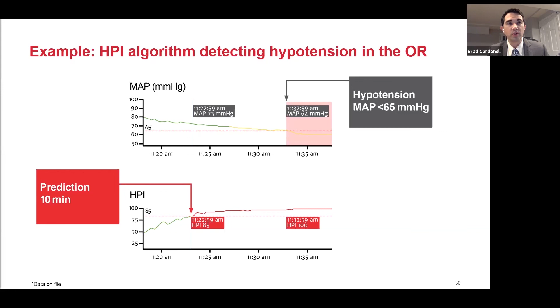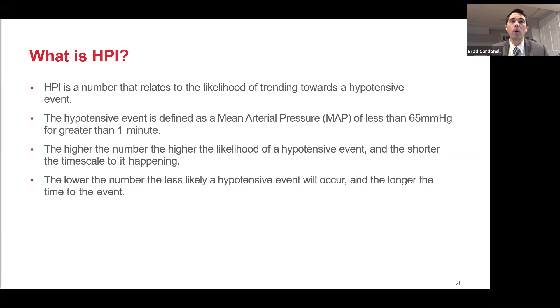So what is HPI? HPI is a number that relates to the likelihood of trending towards a hypotensive event, defined as a MAP less than 65 for greater than 1 minute. The higher the number, the more likely the hypotensive event will occur. And the higher the number, the shorter the time period until that hypotensive event. And the opposite is true. The lower the number, the less likely a hypotensive event will occur, or the longer the time period until a hypotensive event may occur.